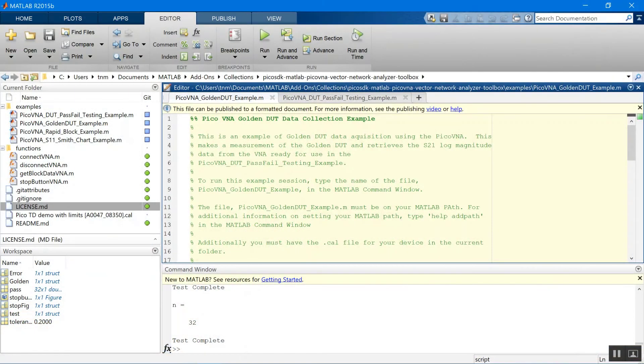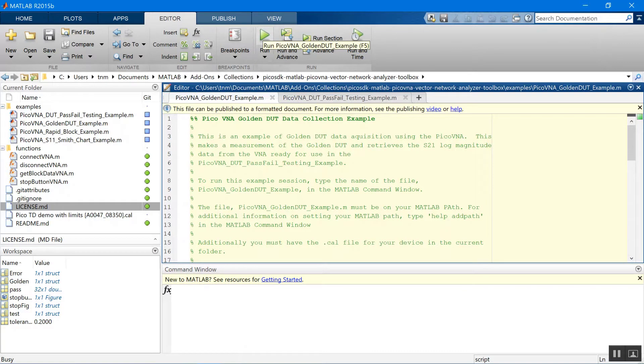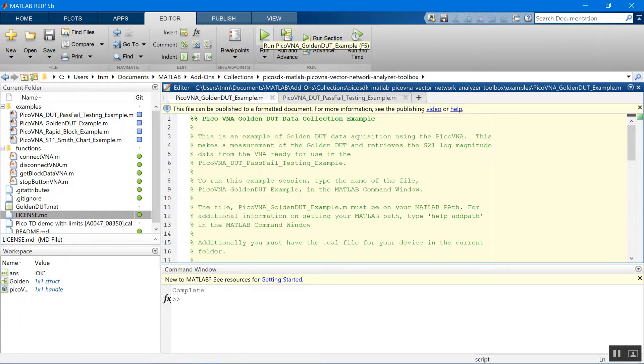It's done a quick test. It's swept this from, what's it sweeping from? 300kHz up to 6 GHz. And it has saved for me here the golden DUT dot mat reference file.